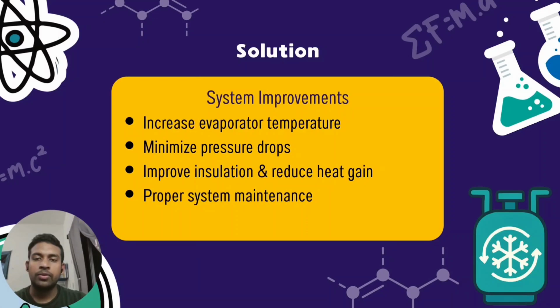Then we can also improve insulation of the refrigerator to lower the chances of heat leaks into the refrigerated area. This will result in less cooling load on the compressor, which then leads to less work in and a higher COP. Moreover, proper maintenance is necessary to allow the system to run smoothly and efficiently. Dirty condenser coils and refrigerant leaks can severely impact the efficiency of the refrigerator. Proper maintenance ensures lower resistance and heat gain in the system. This will make sure that a higher COP can be achieved throughout the system.